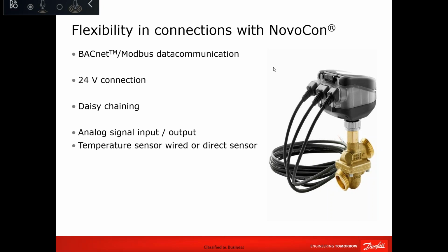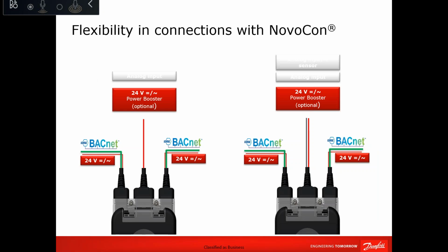So we will see this in detail here. It's based on your application. Sometimes you don't need that, sometimes you need it. You need the actuator, you need the daisy chain, because the daisy chain, which is the looping cable or the looping wire, will carry the communication wires and the 24-volt. So the middle wire will be optional in case you want to boost the power and to use analog local control, because when you use a smart actuator, you can use digital remote control from BMS, and in some cases they still need the local controls hardwired, so it is also available there. So you can go with normal analog cable or with analog cable with built-in temperature sensor. We will see the usage of this later on.